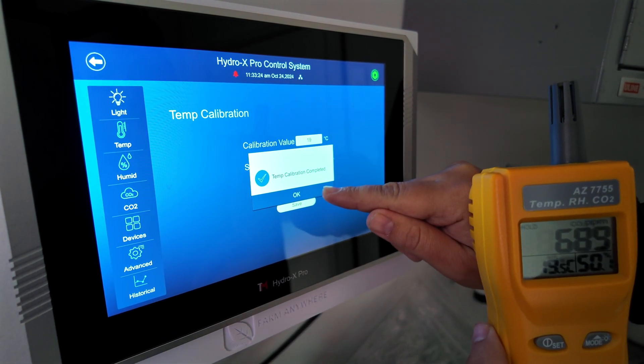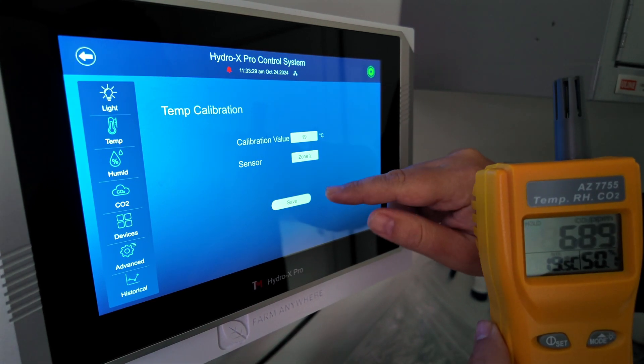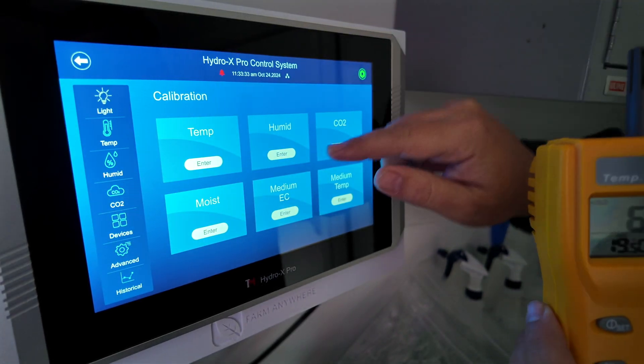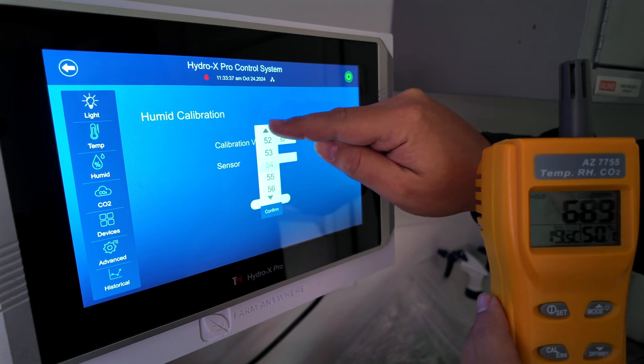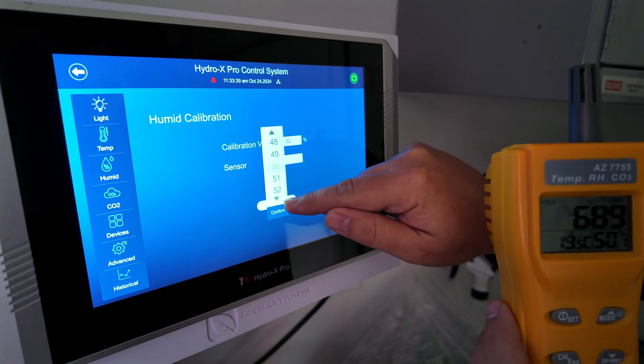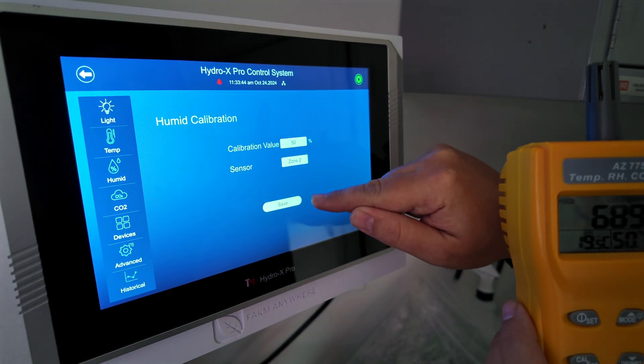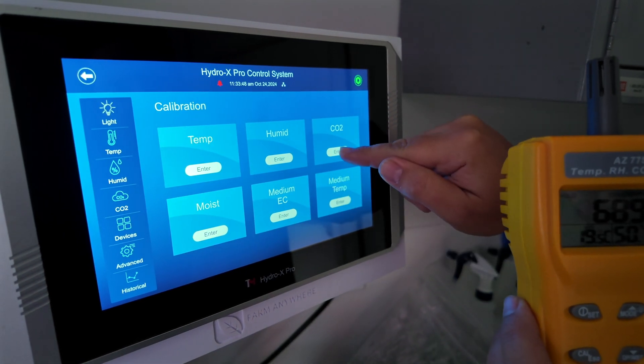When I come back later for Zone 3, I'll select Zone 3 for the next calibration. Now going back into Settings, I'll go to Humidity. I was reading 50% on the hygrometer, so I'll adjust it down to 50, select Zone 2, confirm, and save.